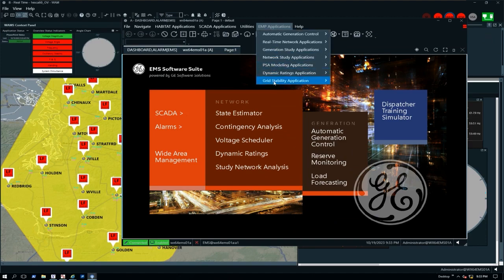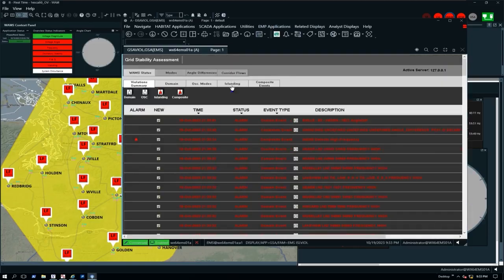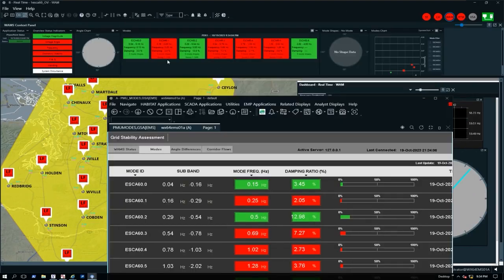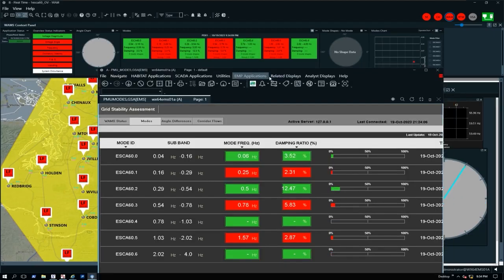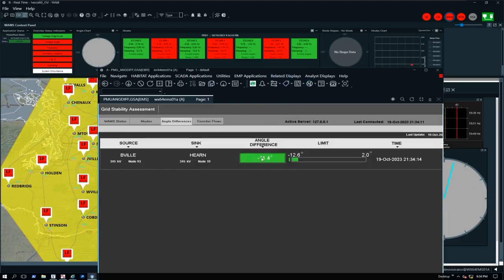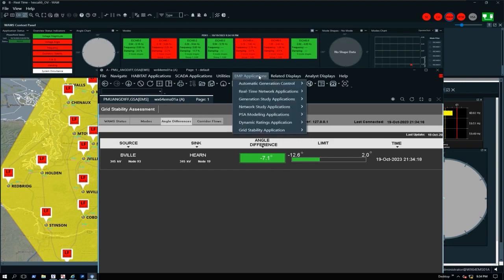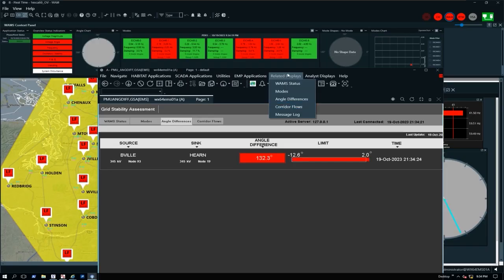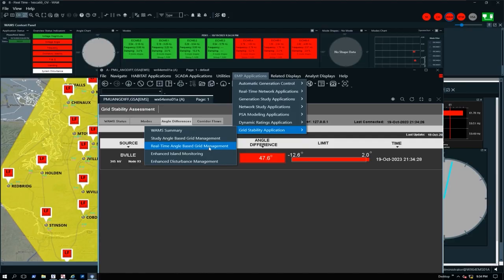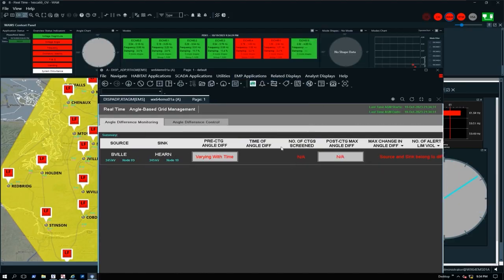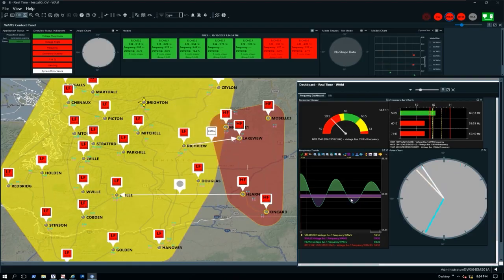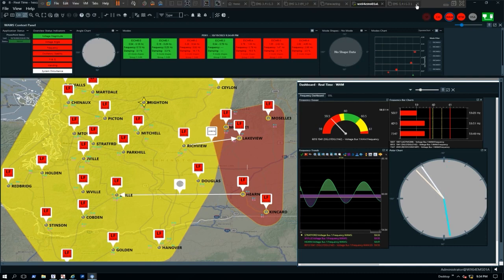I wanted to touch quickly on our WAM system, which also communicates over our proprietary internal ISD link. So we have the ability to bring all of our WAMS alarms into our EMS system. We can monitor those same oscillatory modes, just like we're monitoring them in Vision, and pull that into an EMS context. We can do additional things. If you've got a specific corridor that you're worried about power angles, you can monitor that. And you can also monitor post-contingent angle differences in EMS coming from WAM. But right now I'm in an islanding condition, so it's going to give some poor results. But we're able to represent this geographically and situationally, and we're also able to bring that into our EMS applications as well. So I just wanted to quickly point that out.